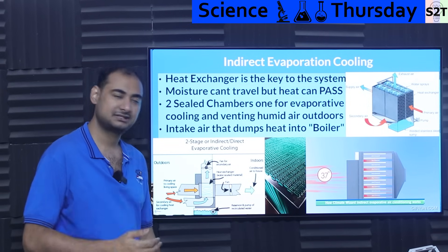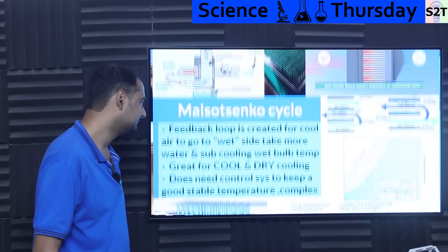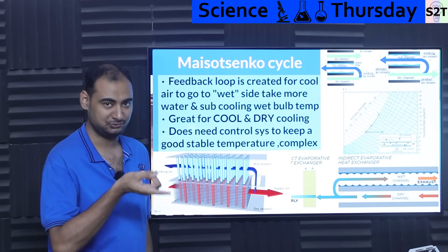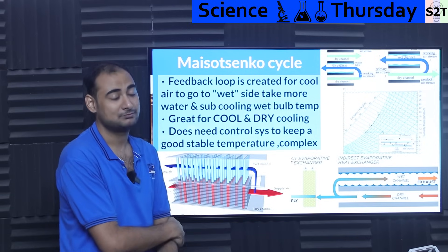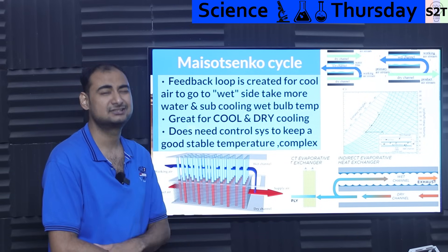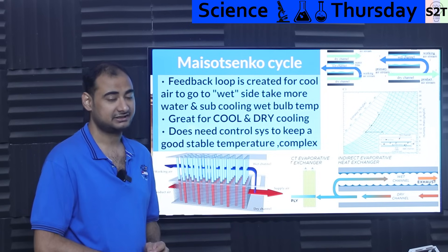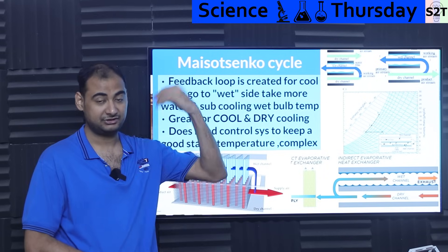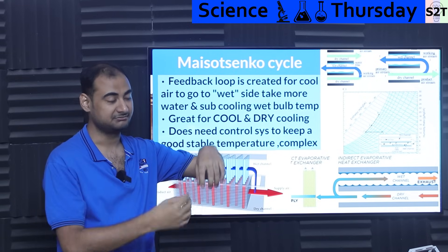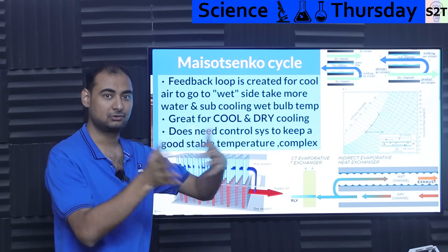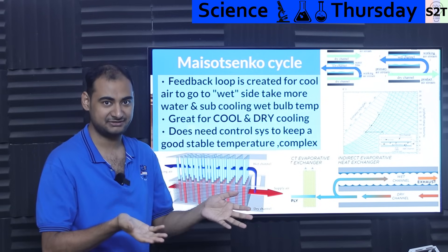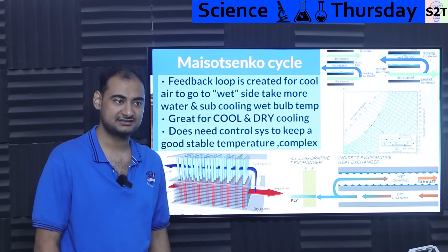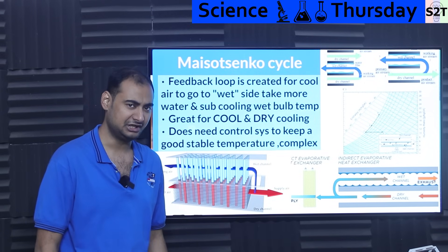Then we go to the M-cycle. Somebody figured out: what if we have a feedback loop? It's not popular in every design and it is messy, but if done correctly it can go below the wet bulb temperature. The wet bulb temperature is the limit you get by putting a wet cloth on a thermometer and blowing air through it — this system can go below that. If the wet bulb temperature is 22°C, this can drop it to 18°C.